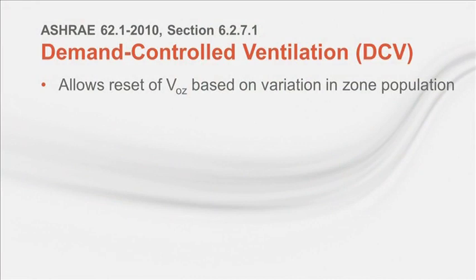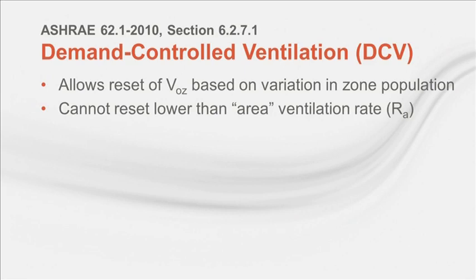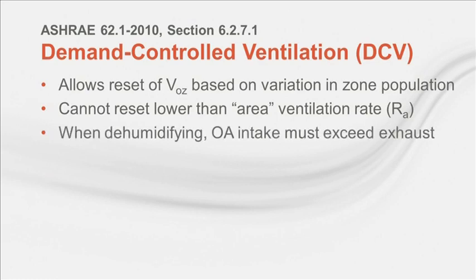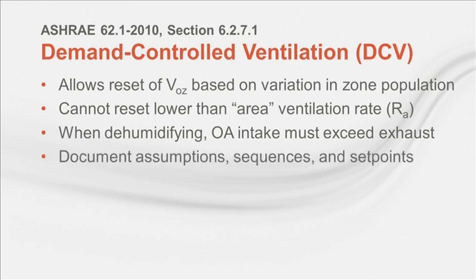Now, the last topic I'll discuss related to Standard 62.1 is demand-controlled ventilation. The standard allows zone outdoor airflow to be dynamically reset based on changing zone population. And it provides some details on implementation. First, the controls can't reduce zone outdoor airflow any lower than the area outdoor air rate, R sub A. Second, when the system is dehumidifying, the intake airflow cannot be reduced to a level that's lower than the coincident exhaust airflow from the system. This requirement indirectly addresses building pressurization. And finally, all assumptions must be documented. This includes control sequences, min and max airflows, and set points.